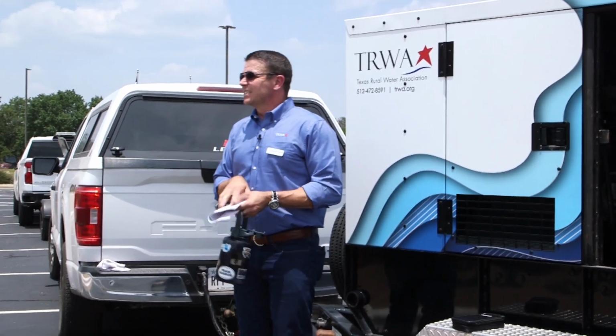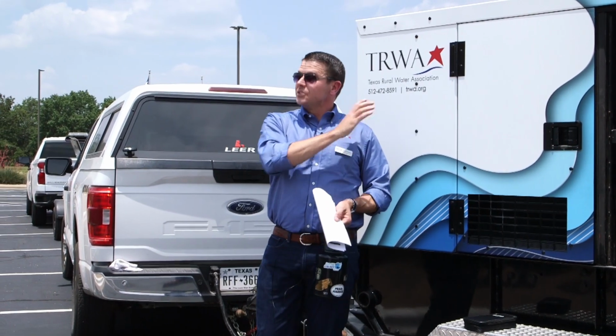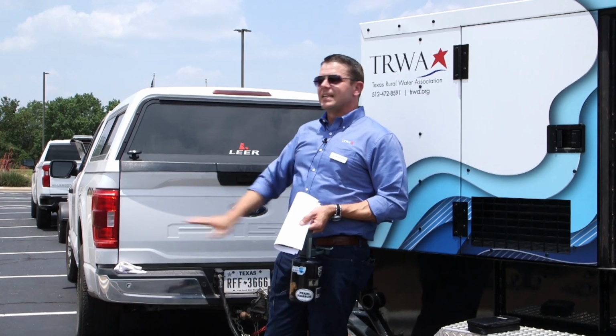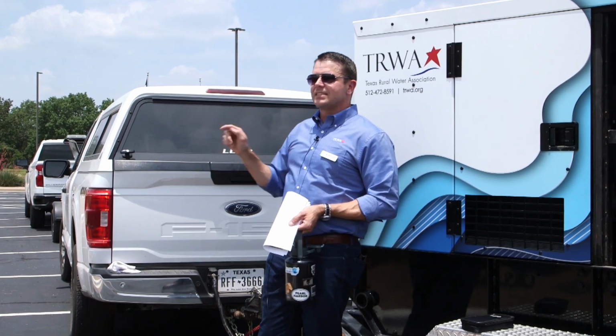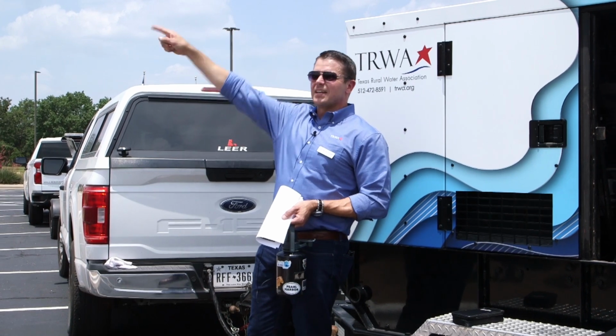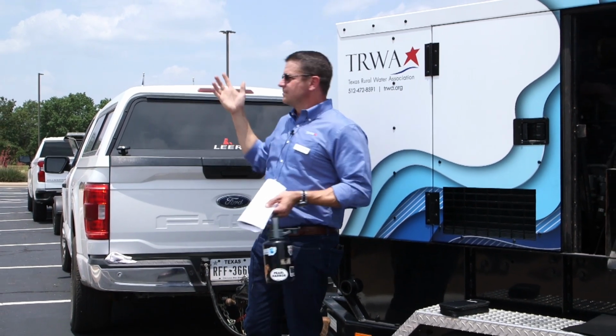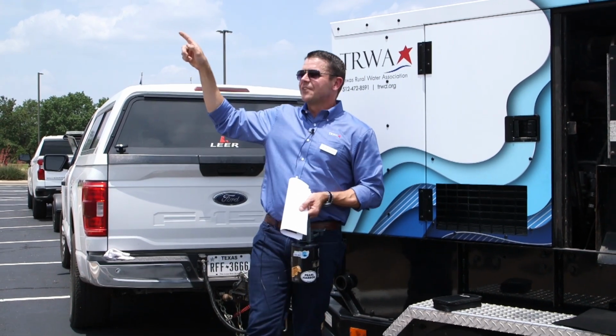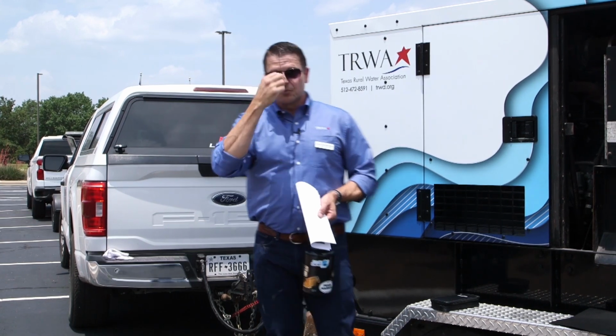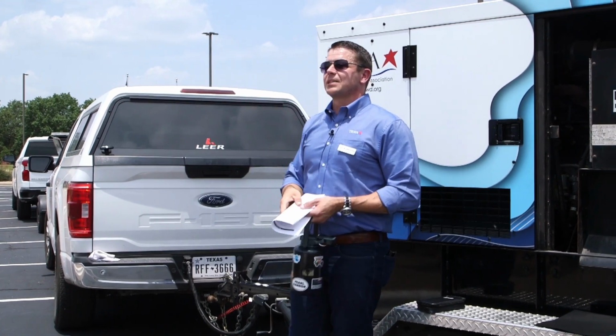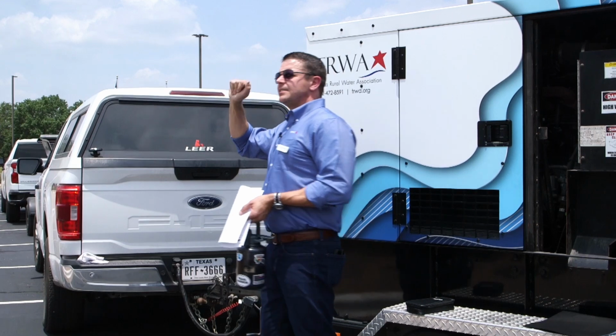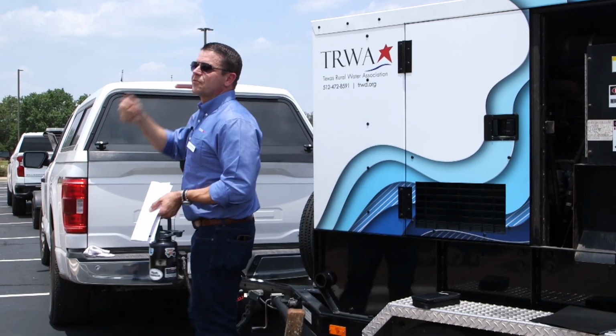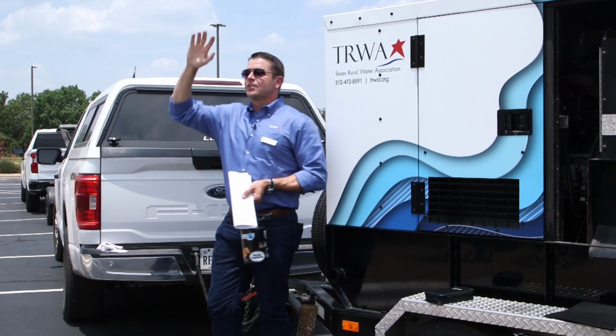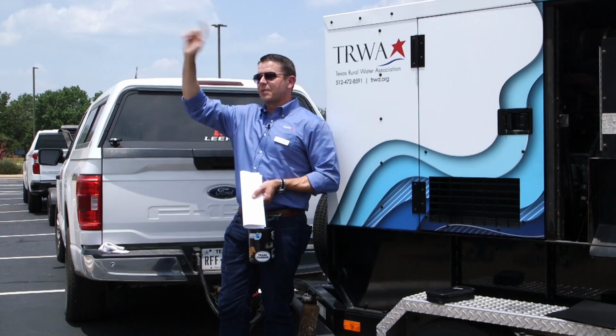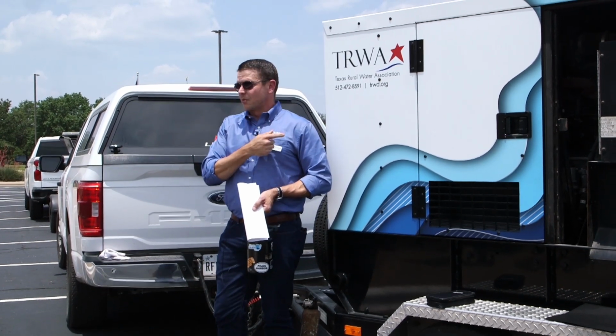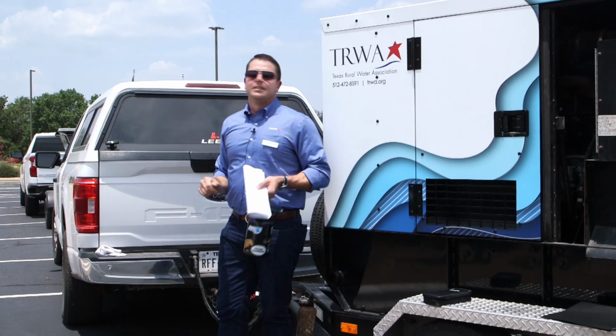There have been too many cases where people hook a generator directly into the panel box, but it's still connected through the meter and backfeeds into the lines. That's a potential hazard for people working on the lines down the road. We witnessed a situation where it actually popped a generator or transformer because we were feeding back and there was still a stick or limb on a line down the road, it popped something because we, I mean the utility, was applying power.